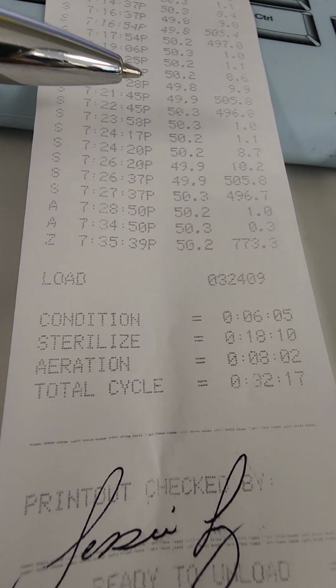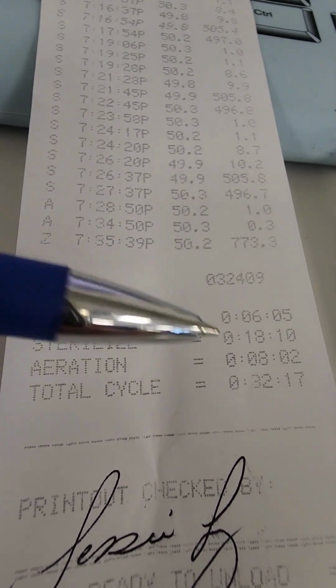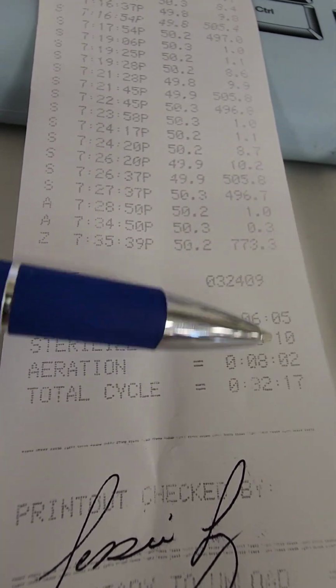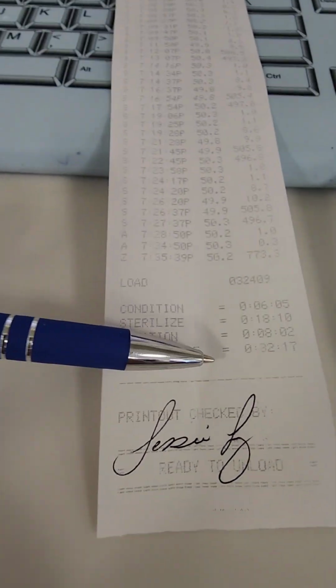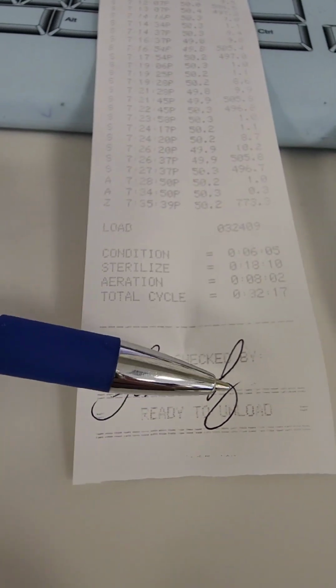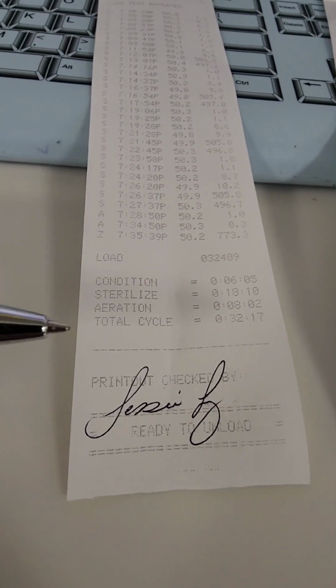Conditioning can fluctuate depending on the package size and what's going on inside of that package. For this cycle right here, it was non-lumen. 18 is about the average time for how much hydrogen peroxide's in that chamber. And then, of course, a signature for completion.